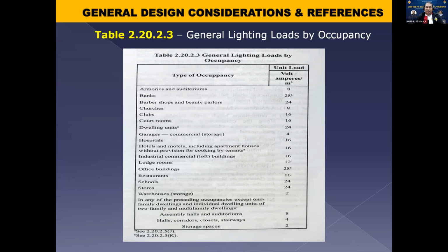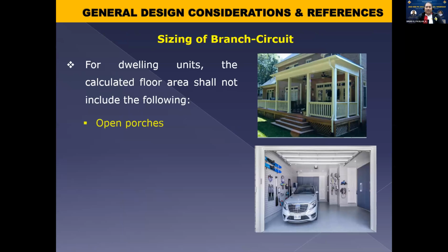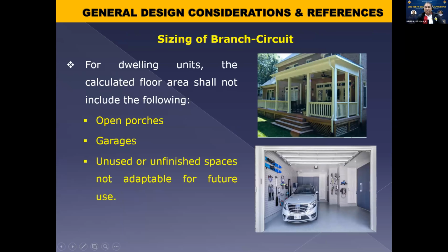So ito yung table guide natin, okay? So may exemptions lang, hindi included. Excluded yung mga open porches like this one. I don't know if we have houses like this one, but usually in the US they have this open porch. Meron siguro yung mga malulumang bahay natin, yung mga pre-war era, meron mga open porch, so hindi yan kasama sa load density area, occupied area, or even garage.